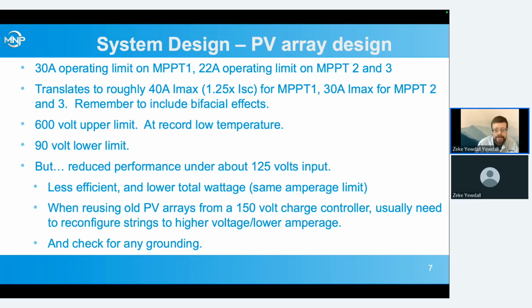We also want to make sure that we never exceed the 600 volt upper limit. And remember, this is at record low temperature, not at STC conditions. So you've got to do the math and calculate what is the actual open circuit voltage of the array on that cold winter day. Typically 15 to 25% higher. In more moderate climates, it might only be maybe 10% higher.